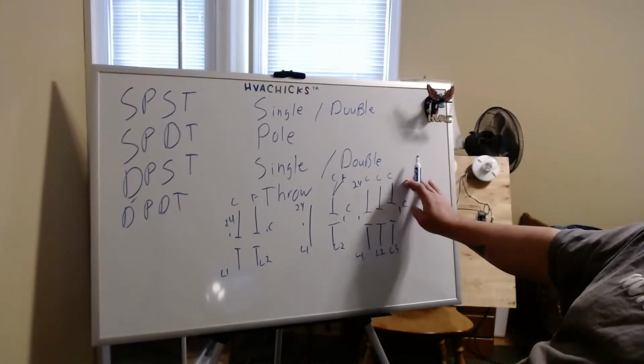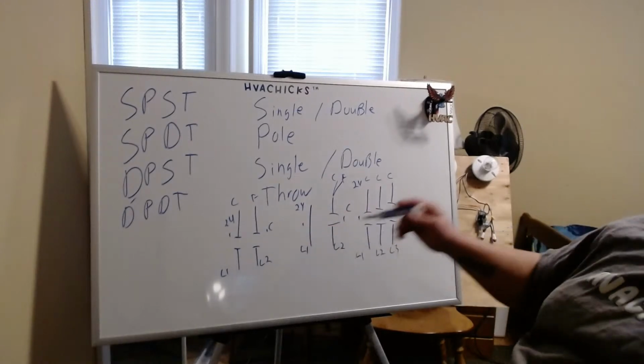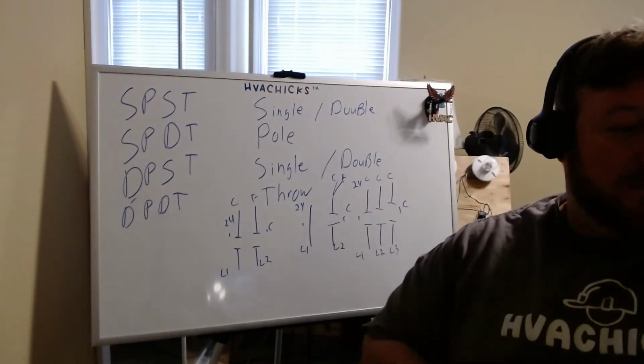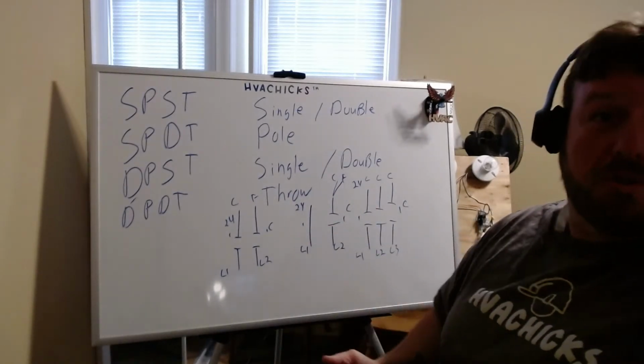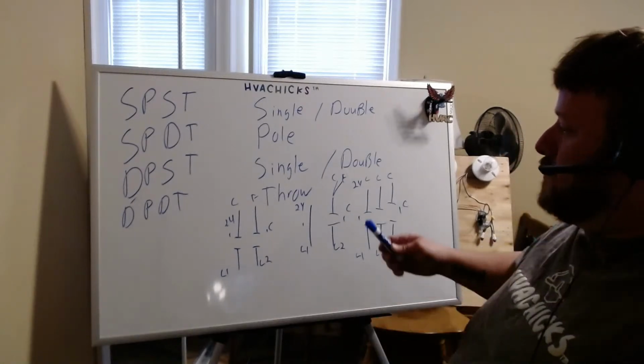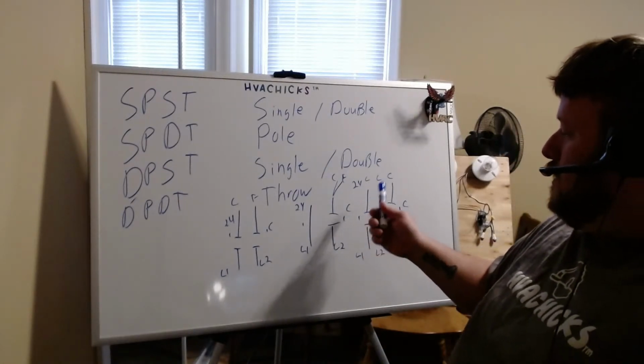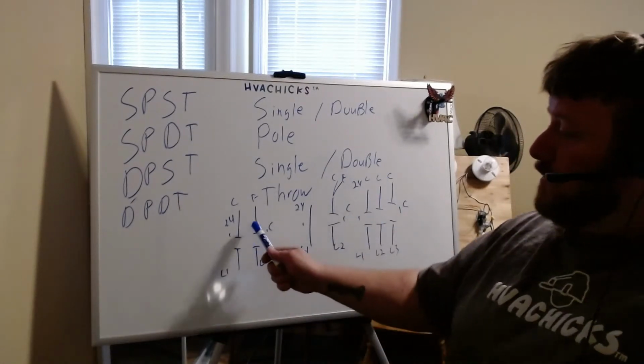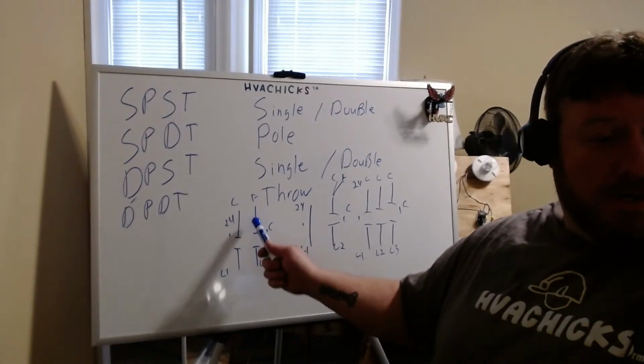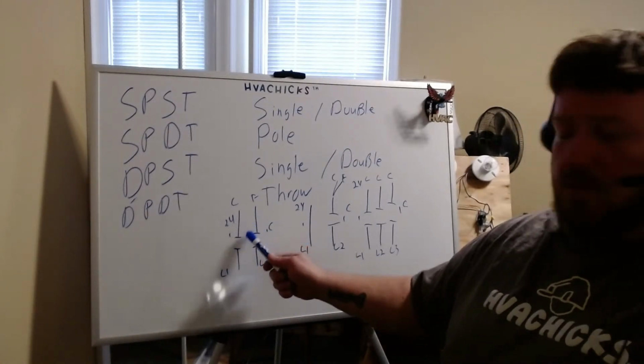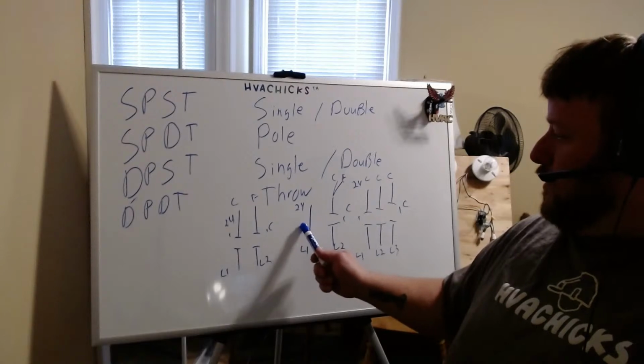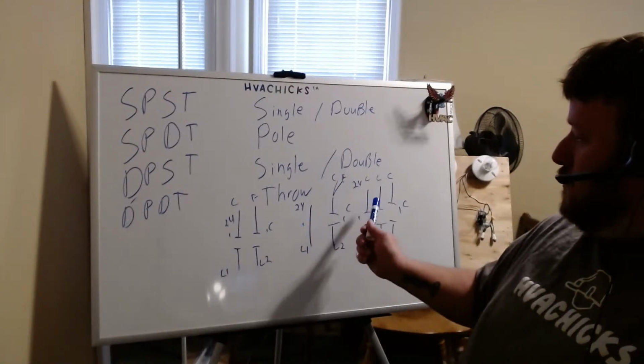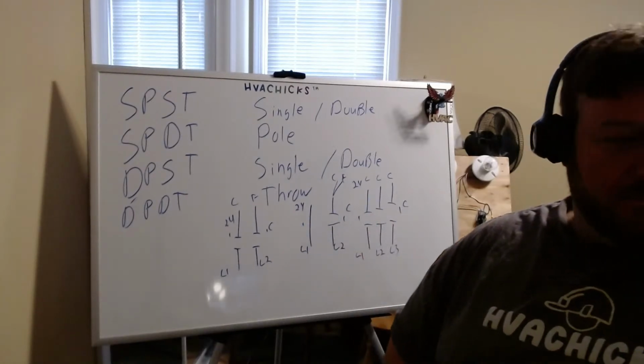Your condenser fan motor may be on a double pole contactor. It depends on the type of system you're messing with, how the manufacturer's wired it up, and what controls they're using. I know a lot of package units that will use 3-pole contactors. I also know they'll use double pole. Carrier is notorious for putting a double pole contactor and a single pole contactor in their systems and not using a 3-pole contactor.